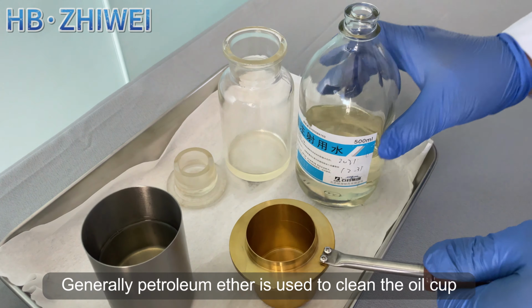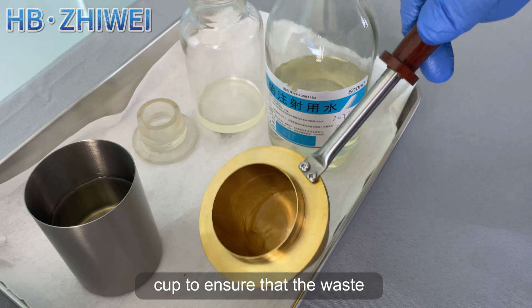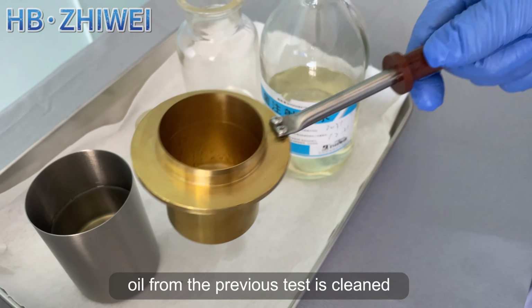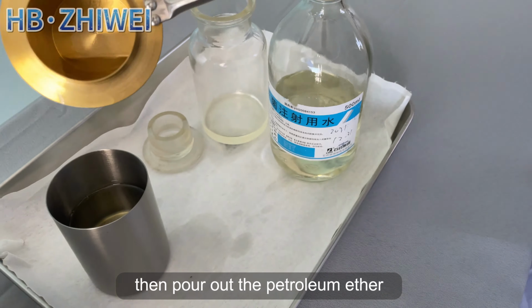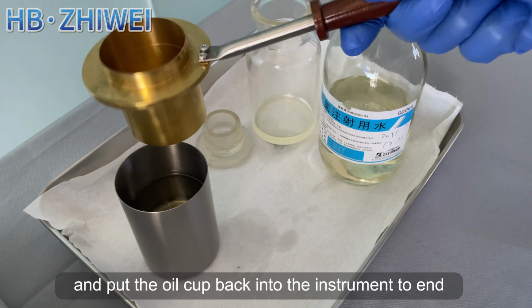Generally, petroleum ether is used to clean the oil cup. Pour the prepared petroleum ether into the oil cup. Customers can pour more petroleum ether when cleaning. Make sure the oil cup is clean. Let the petroleum ether shake repeatedly in the oil cup to ensure that the waste oil from the previous test is cleaned. Then pour out the petroleum ether and put the oil cup back into the instrument to end.